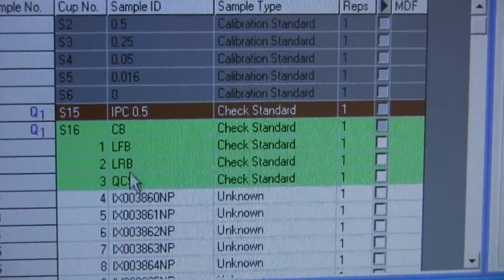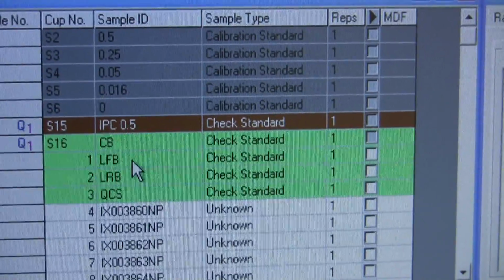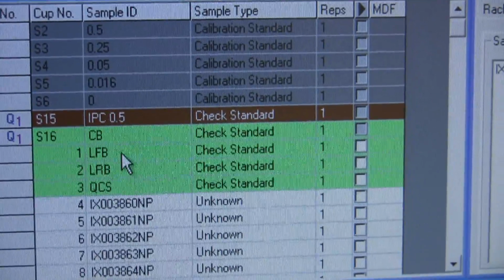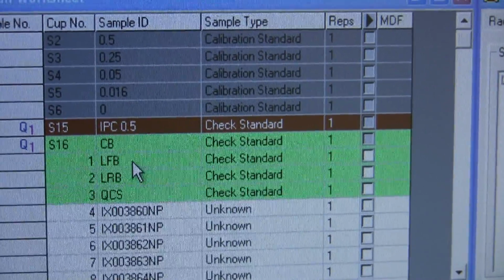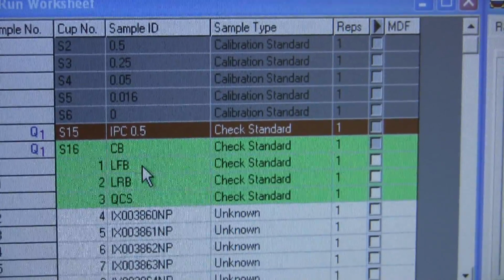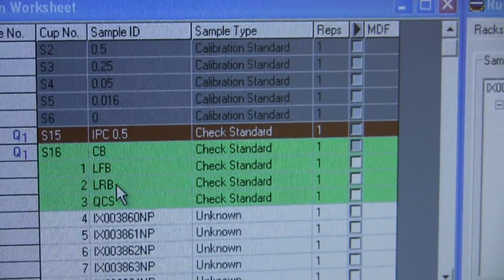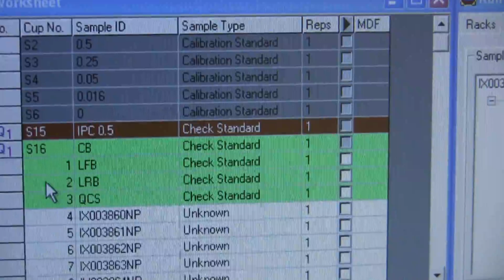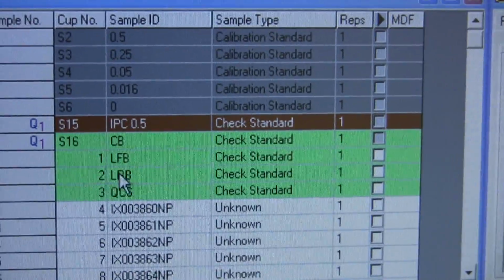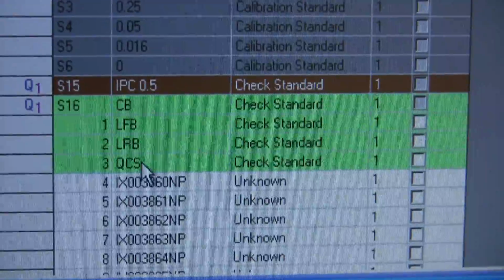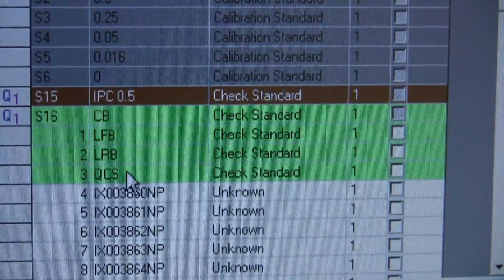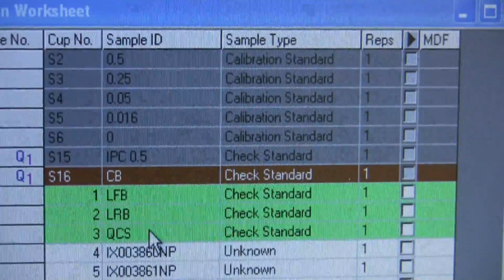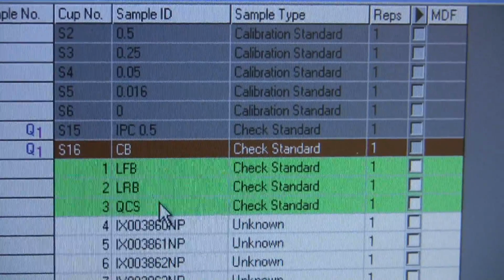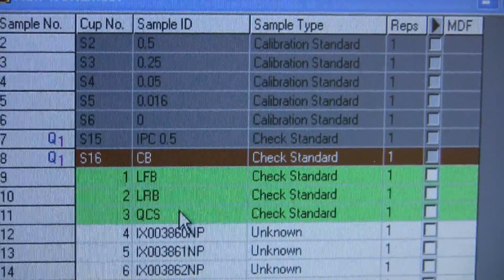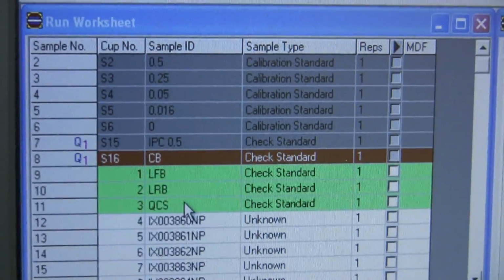These first three green ones here are a lab fortified blank, which is a test of our spike solution. We spike one sample every 10 to show that we can recover the phosphorus and there isn't a matrix interference. And then a laboratory reagent blank, which shows that we didn't have any issues with contamination when we set this up. And then this QCS is another source of phosphorus, different from these standards, and we check that just as a second check against the standards we've made. We purchase a standard from another company or vendor, and it's just a double check on what we're doing.